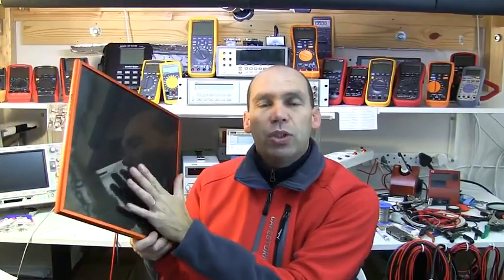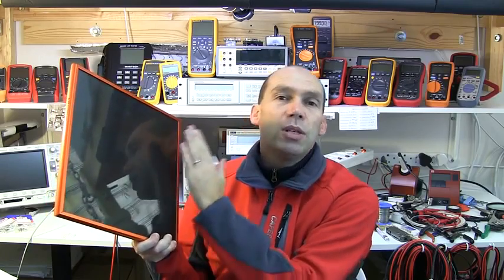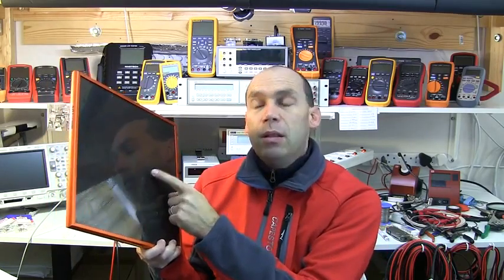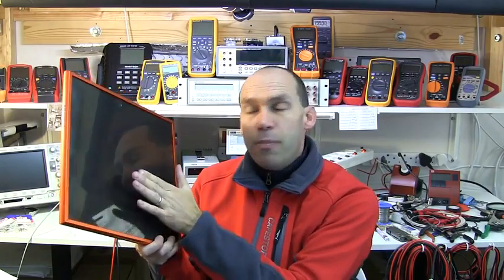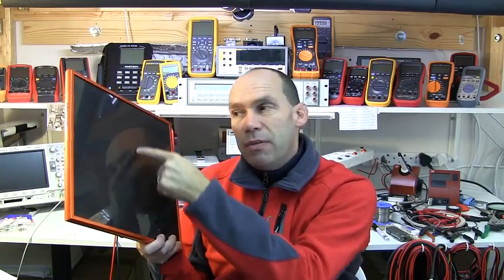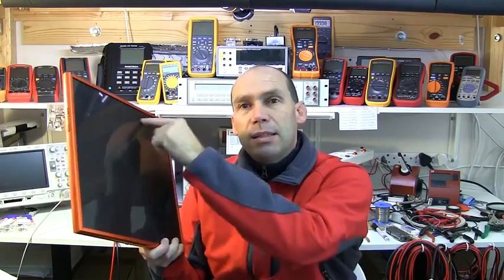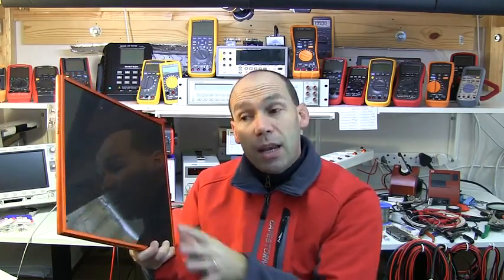If you have partial shading on any solar panel, in particular a mono or a polycrystalline panel, if you just cover up a few of those cells, you almost lose all the power on your panel. Whereas on an amorphous panel, if you only partially cover the cell, whatever percentage you cover, that is roughly the percentage of power you'll lose. So you only lose the power from the area that's covered, because it hasn't got individual cells which are linked together, and therefore if you partially cover one cell, it cuts the power going to all of them. You can in the monos and the polys get bypass diodes, but nonetheless you are going to lose power.